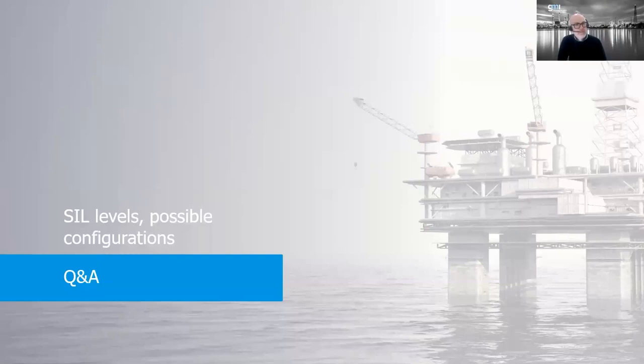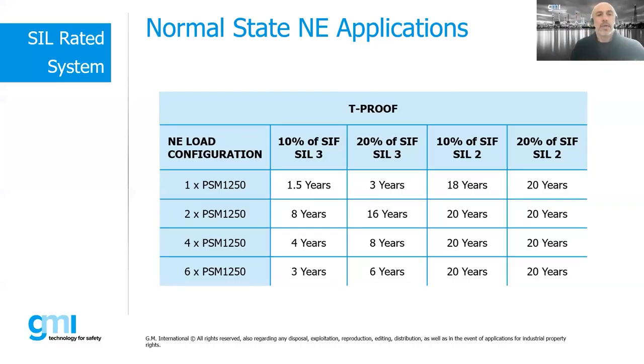And the next question is related to the possible configurations to reach the different SIL levels with our safety power supply system. If you look here at normally energized, you use one power supply, depending on what percentage of the SIF you are taking into account and what the SIL level is. So let me highlight this point. Here we have SIL3 and SIL3. Here we have only SIL2. So 10%, 20% of the SIF. You use one power supply. With 10% it can be a 1.5 year proof test, after which the SIL3 is gone, so from SIL3 you move to SIL2. If you take 20% of the SIF it is 3 years. While for SIL2 you can use it for the whole lifetime of the power supply.